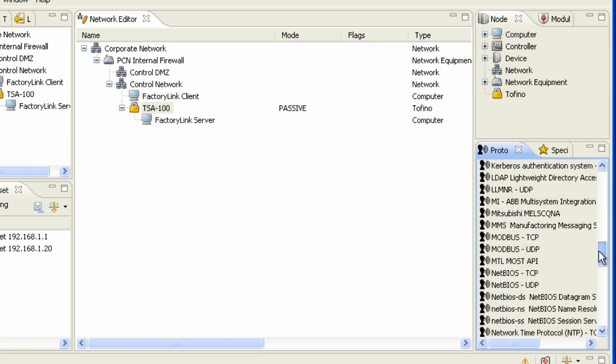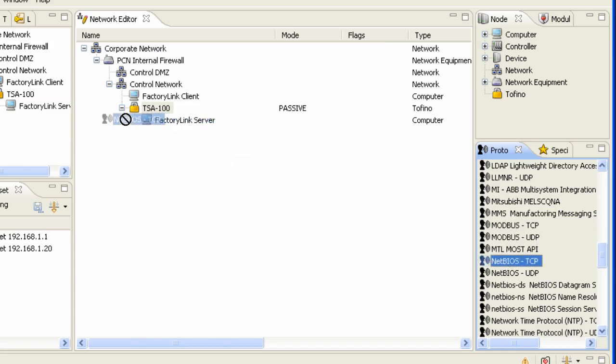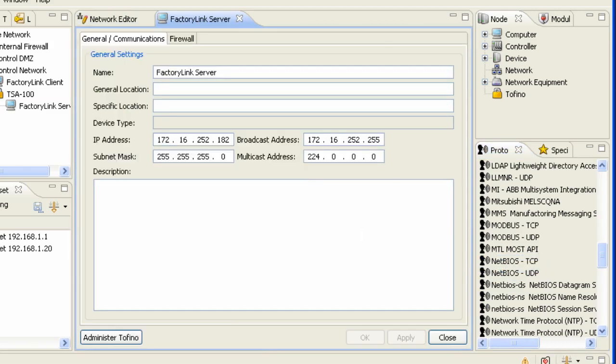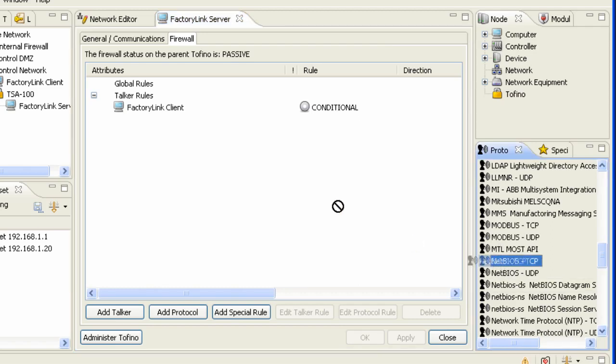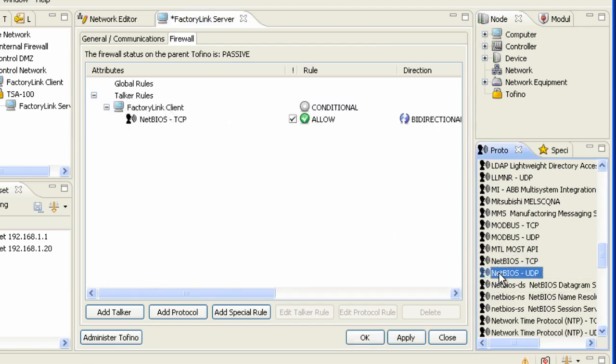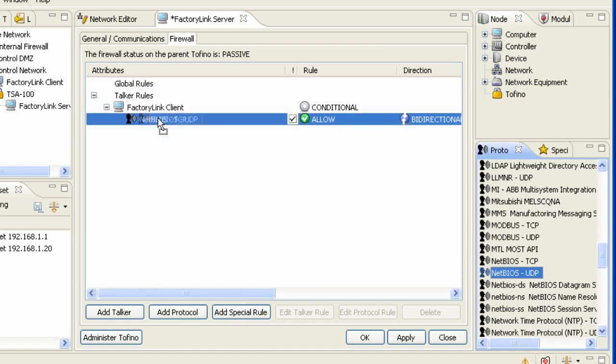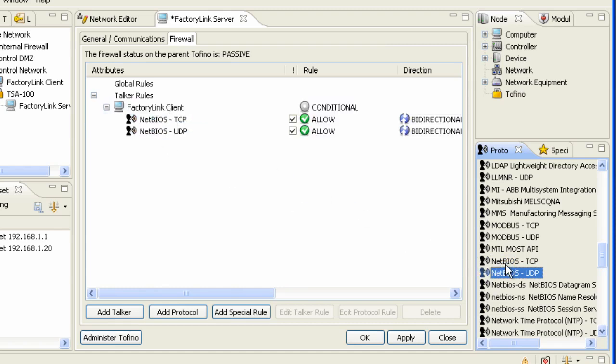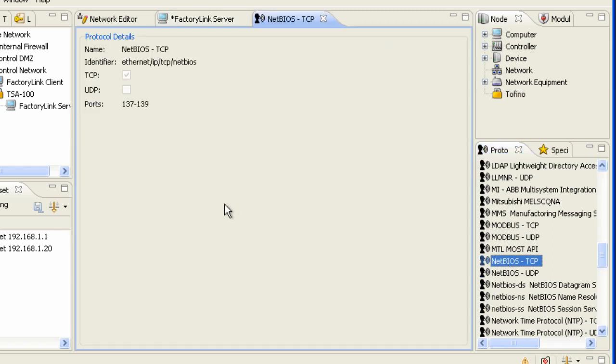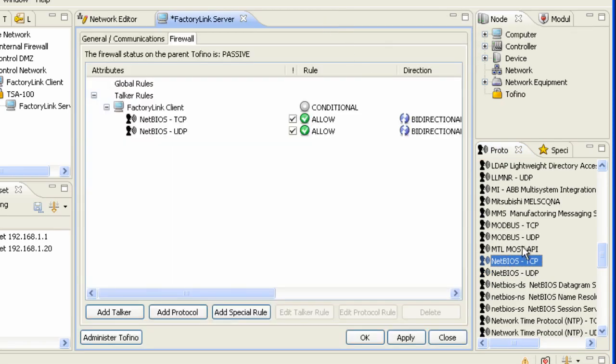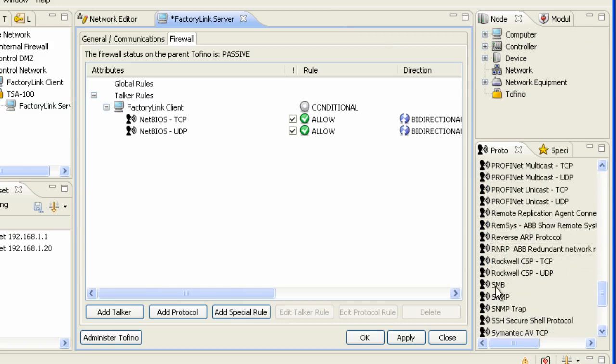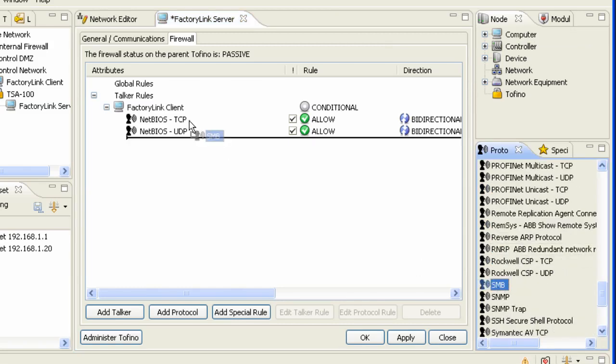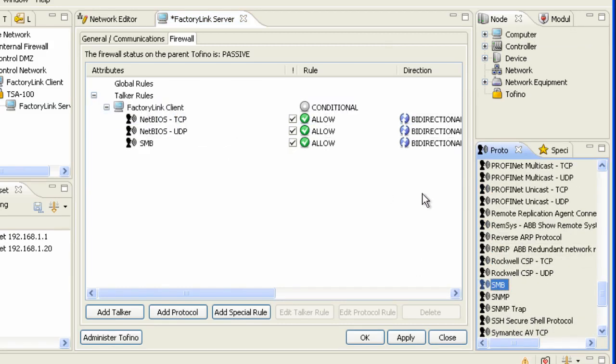First of all, we need to address NetBIOS in this case because it is used between the clients and server within the factory link environment. So I'm going to come over here on the firewall and I'm going to take my NetBIOS TCP and UDP, which is, if we take our cursor over here, we can see that it's TCP and UDP ports 137 through 139. I'm also going to come down here and I'm going to bring over SMB, which is used for file sharing. And the client does communicate with the server for exchange of graphic files.